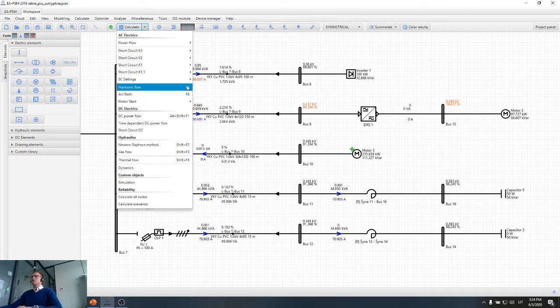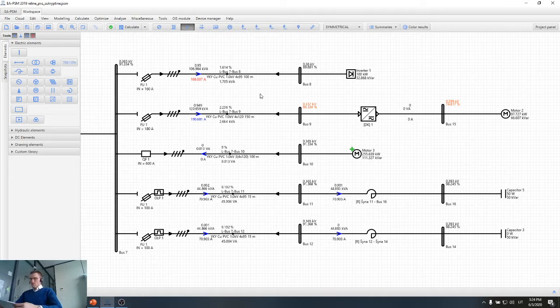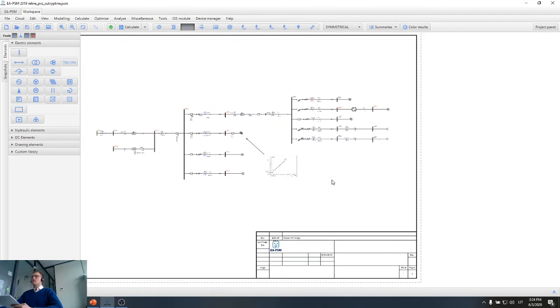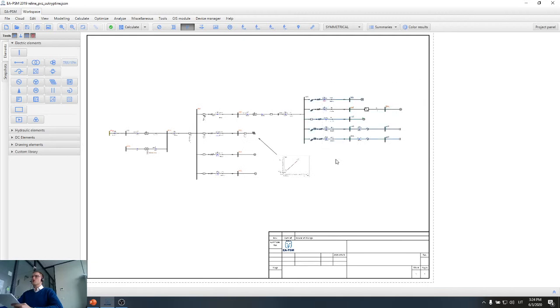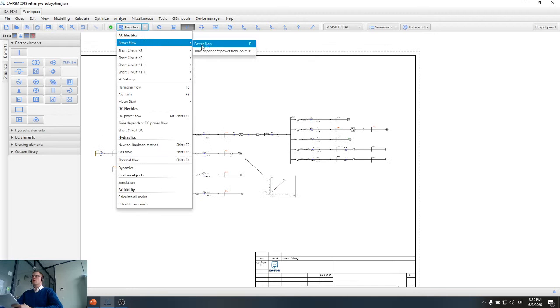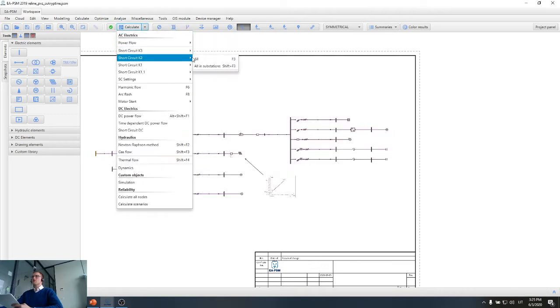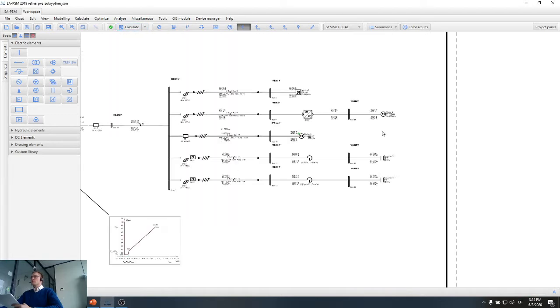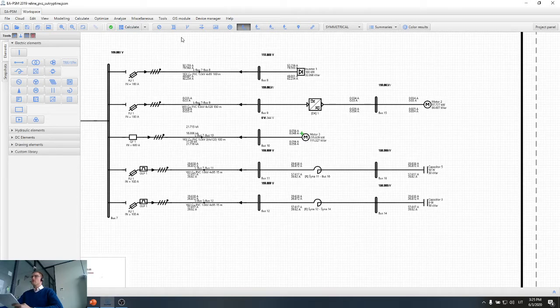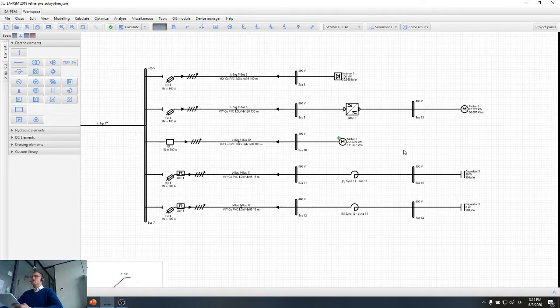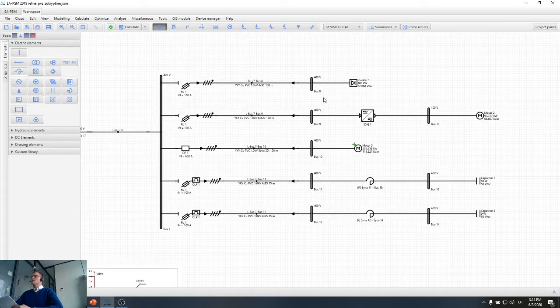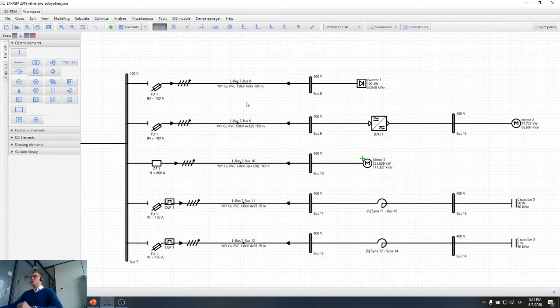So basically, now this is just a quick review. Let's go on with the protection coordination itself. I think I will start from the low voltage network protection coordination, and step by step we will move to medium voltage as well. As I have mentioned, for our protection coordination study we will need power flows, short circuits, result calculations, and also motor startings. I already calculated motor starting currents for this motor, so we will use them and I will not recalculate them. So let's start from the inverter protection coordination.